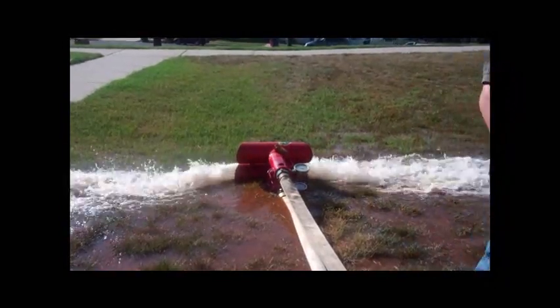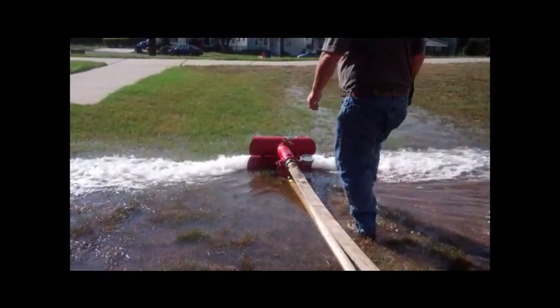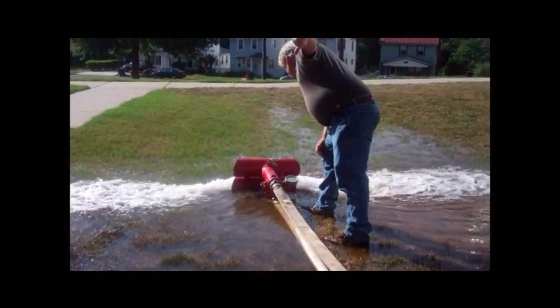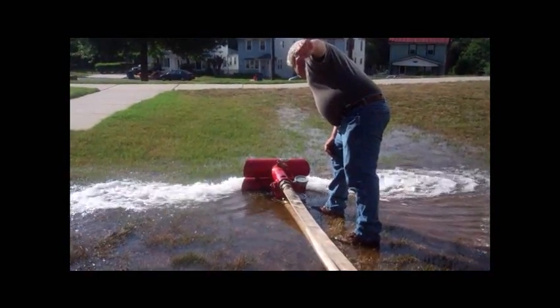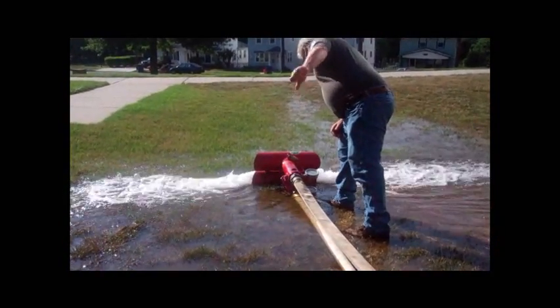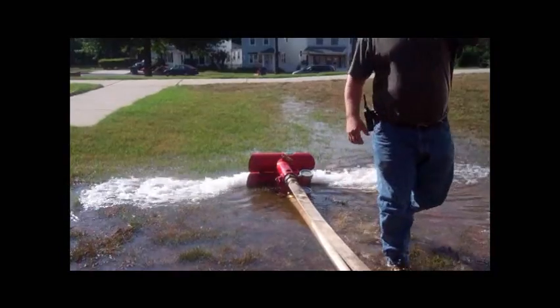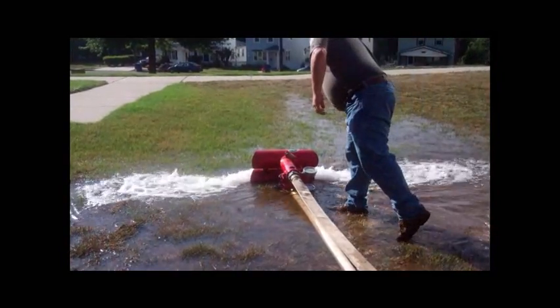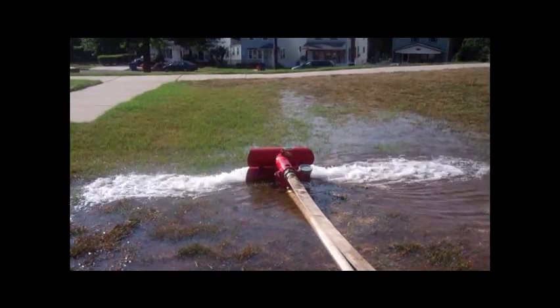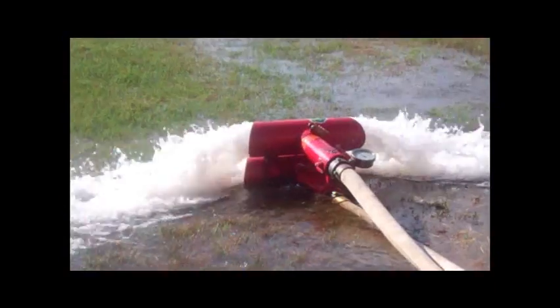Once the churn test is complete, there are three separate test measurements taken. The first is at 50% of the pump's rated capacity. The second is at 100% of the pump's rated capacity. The third test is at 150% of the pump's rated capacity. This is done by controlling the amount of water flowing through the hose monsters and taking readings back at the fire pump and the fire pump controller.